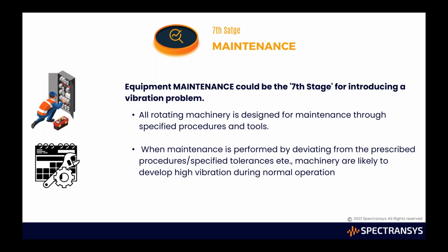There are stringent processes as to how the machine should be dismantled, how it should be assembled, what clearances are checked at various stages, and the specific tools that need to be used for assembling and putting back the components. So if the procedures are deviated from, and if you are not using skilled, trained manpower for all those things, then these maintenance activities can sow a seed for the vibration problem.